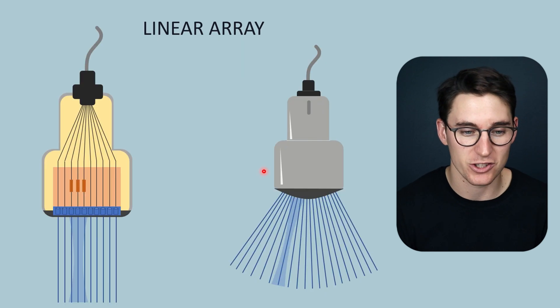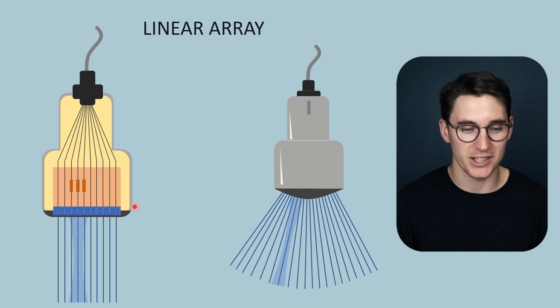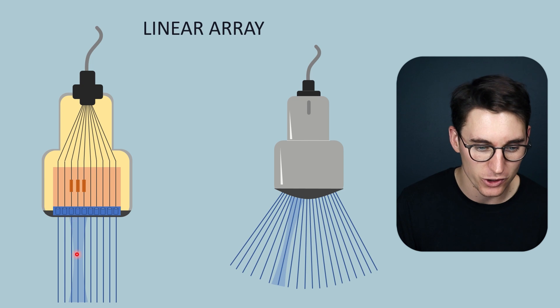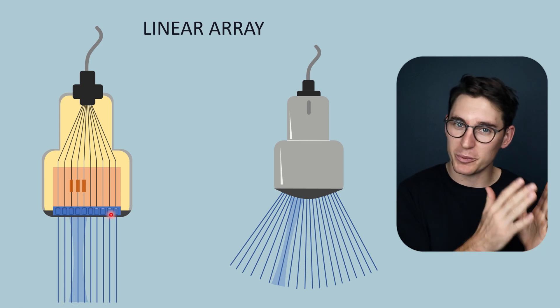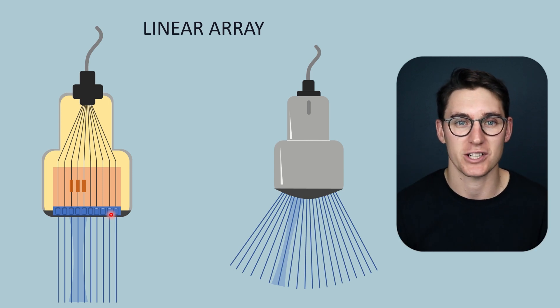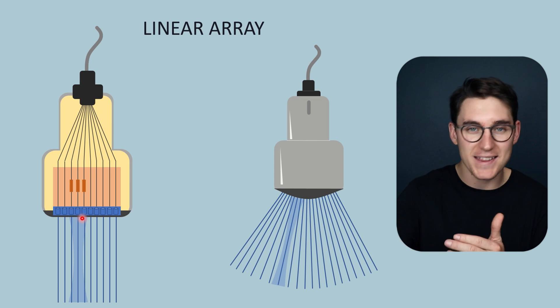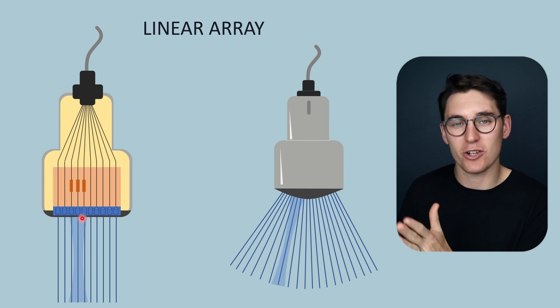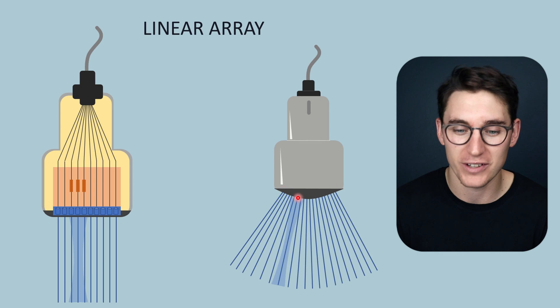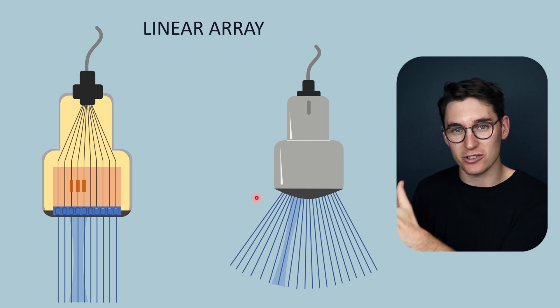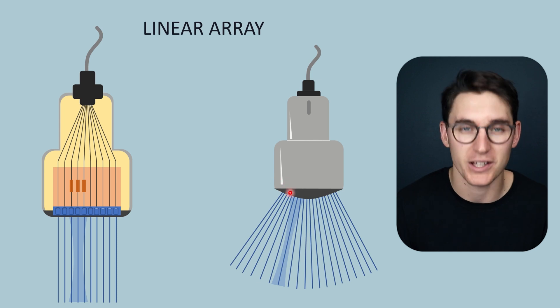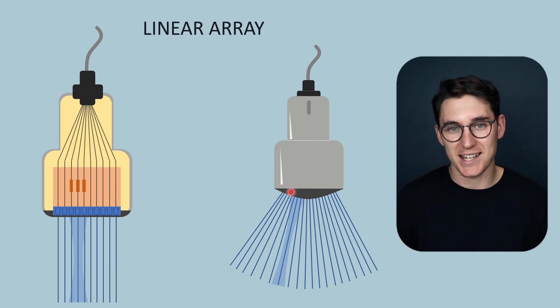Looking at the linear array: with a flat sequential linear array, we fire three transducer crystals to create a small part of our ultrasound beam, then shift across the transducer elements over time to build our B-mode image that appears as a live image on screen. Each time we fire a group of elements, we get A-mode data back and stitch together all those A-mode data points to create our brightness image. The same thing happens in the curvilinear array, but the PZT crystals have a curved shape, so the beam comes off perpendicular to the probe face but diverges as it heads out into the tissues.